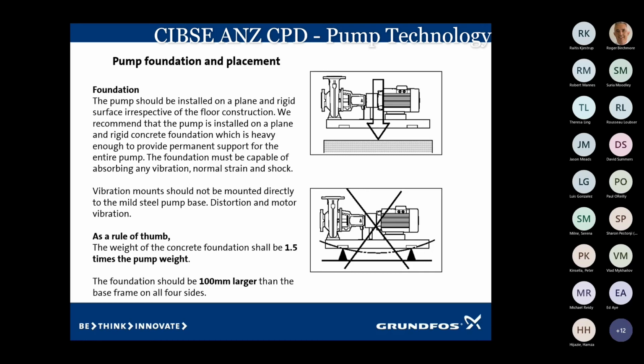Pumps on foundations and bases. When we pull a pump down, it's got to be secured hard down to the foundation. It's got to be flat, nice and level and flat. If that foundation has got any humps or bumps in it, what you're going to do is when you pull the pump base down, you can distort it, or you can put pressure on different corners, and that then is going to load onto the pump and the motor. So then eventually you're going to start to get some wearing in the bearings, or you're going to get impeller rubbing on the pump housing.